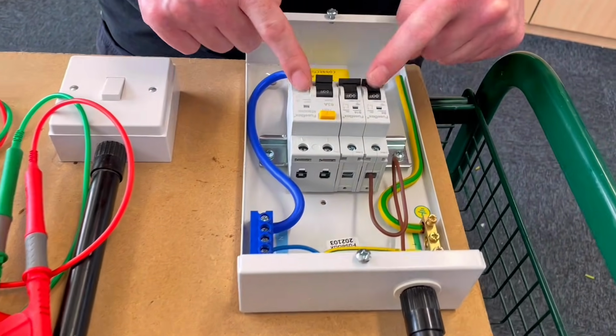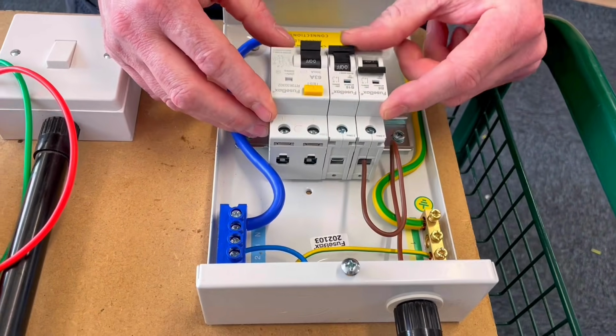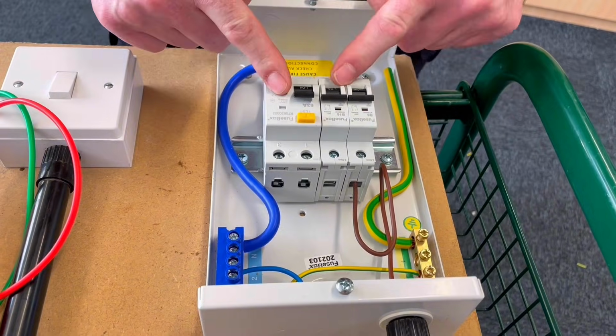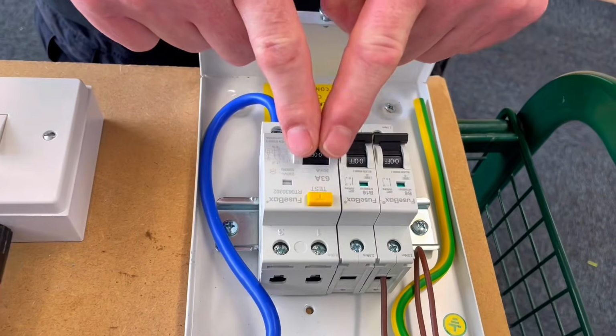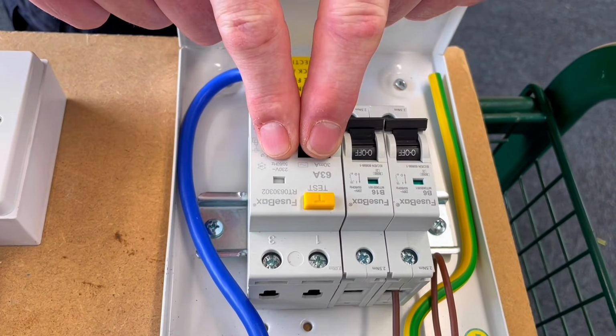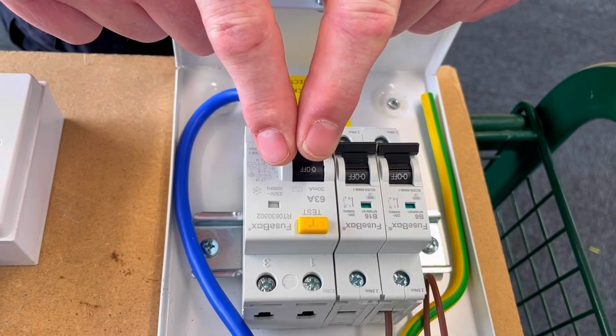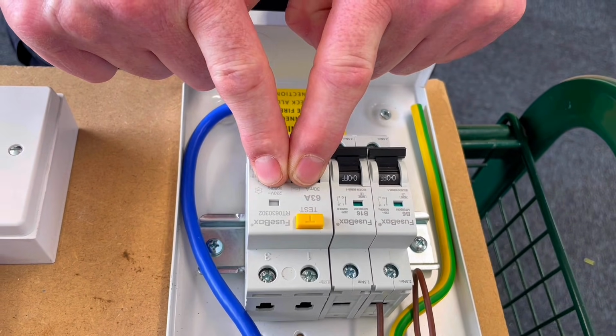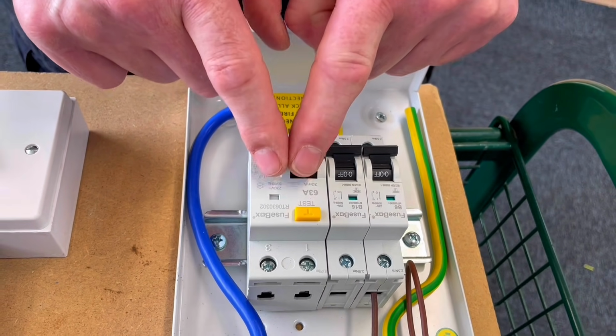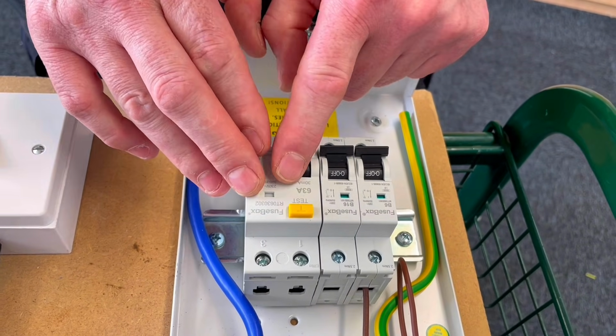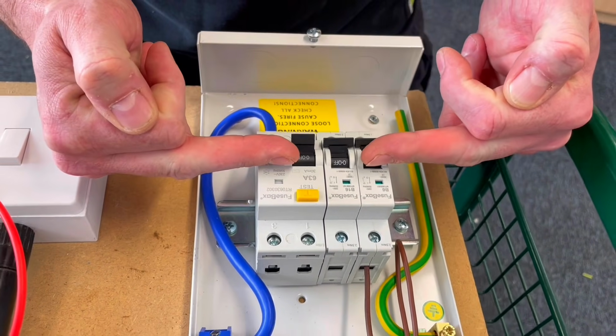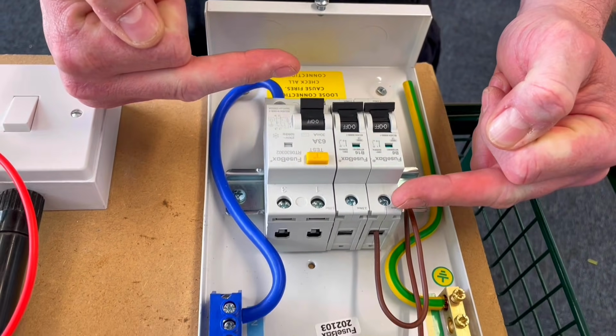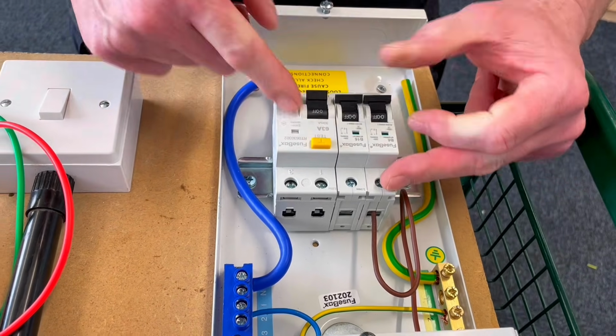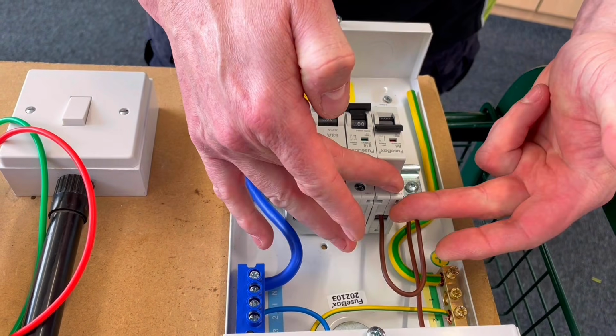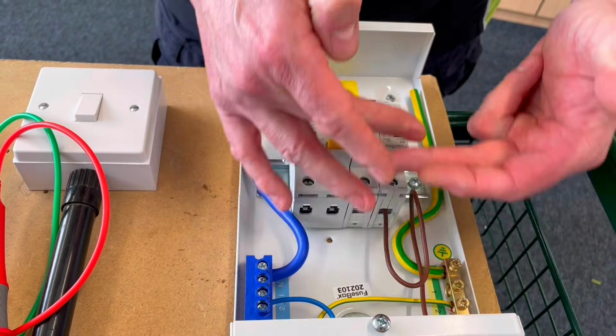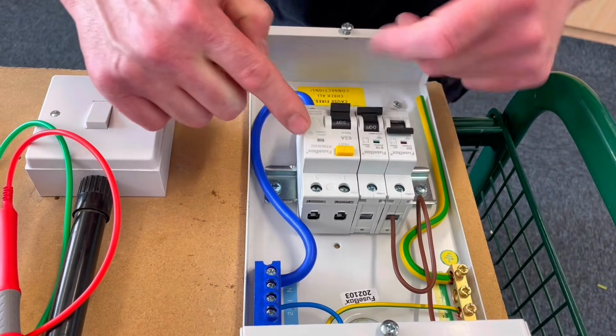So if we look in here, these are also effectively switches. So we don't want these switches in the on position either, because these components here, this one here being an RCCB, contain electronic components, and we do not want to pass 500 volts DC through those because they could be damaged. So we're going to make sure everything is in the off position, and we're going to test from the outgoing side here with these off, because if we left it on, the 500 volts would pass up and through the circuit as well as down and across the bottom of the RCCB.